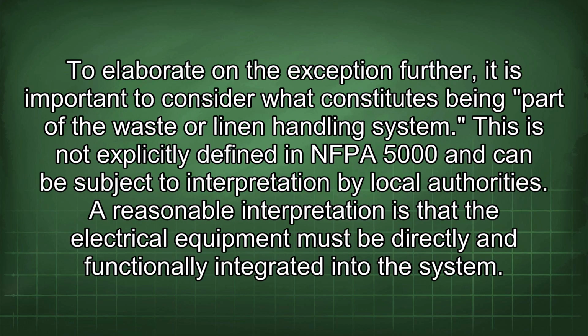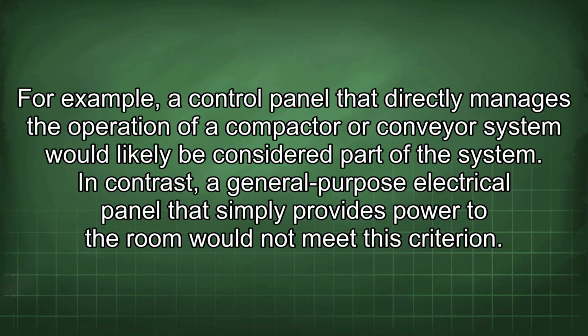To elaborate on the exception further, it is important to consider what constitutes being part of the waste or linen handling system. This is not explicitly defined in NFPA 5000 and can be subject to interpretation by local authorities. A reasonable interpretation is that the electrical equipment must be directly and functionally integrated into the system. For example, a control panel that directly manages the operation of a compactor or conveyor system would likely be considered part of the system. In contrast, a general-purpose electrical panel that simply provides power to the room would not meet this criterion.